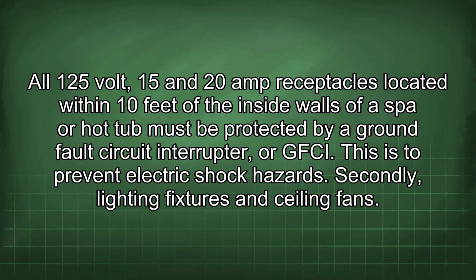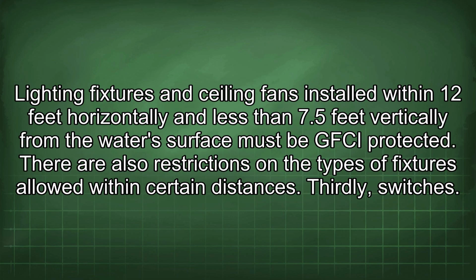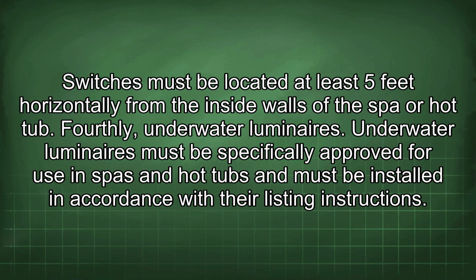Secondly, lighting fixtures and ceiling fans. Lighting fixtures and ceiling fans installed within 12 feet horizontally and less than 7.5 feet vertically from the water's surface must be GFCI protected. There are also restrictions on the types of fixtures allowed within certain distances. Thirdly, switches. Switches must be located at least 5 feet horizontally from the inside walls of the spa or hot tub. Fourthly, underwater luminaires. Underwater luminaires must be specifically approved for use in spas and hot tubs and must be installed in accordance with their listing instructions.